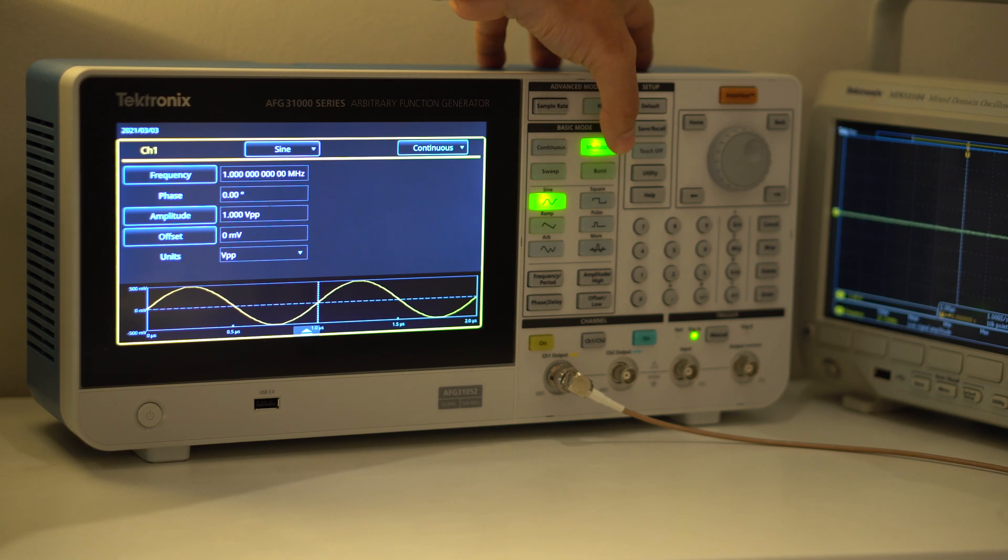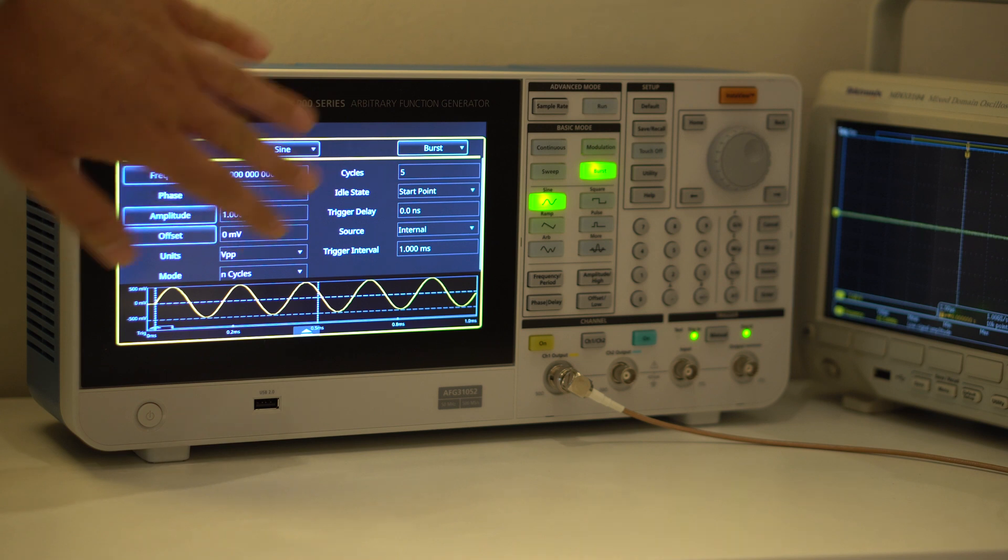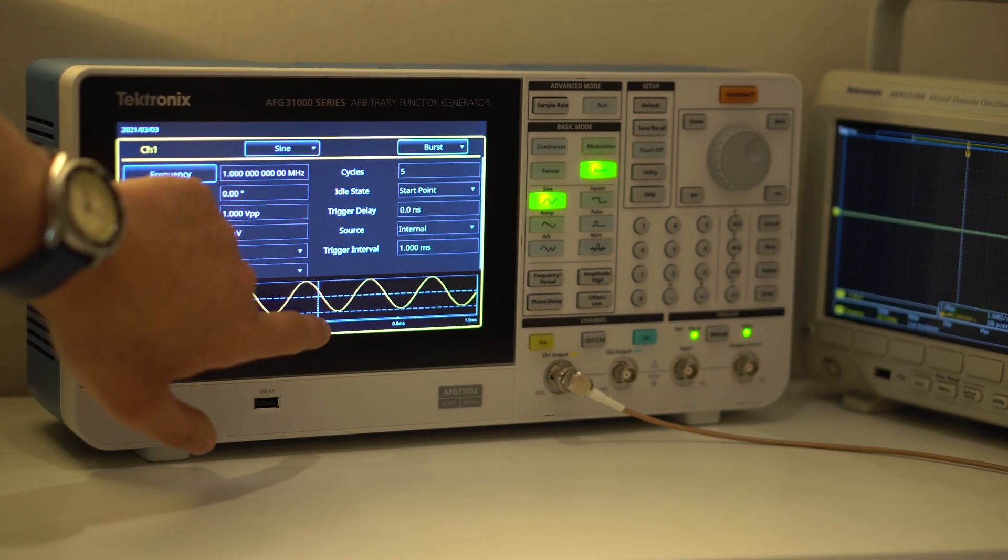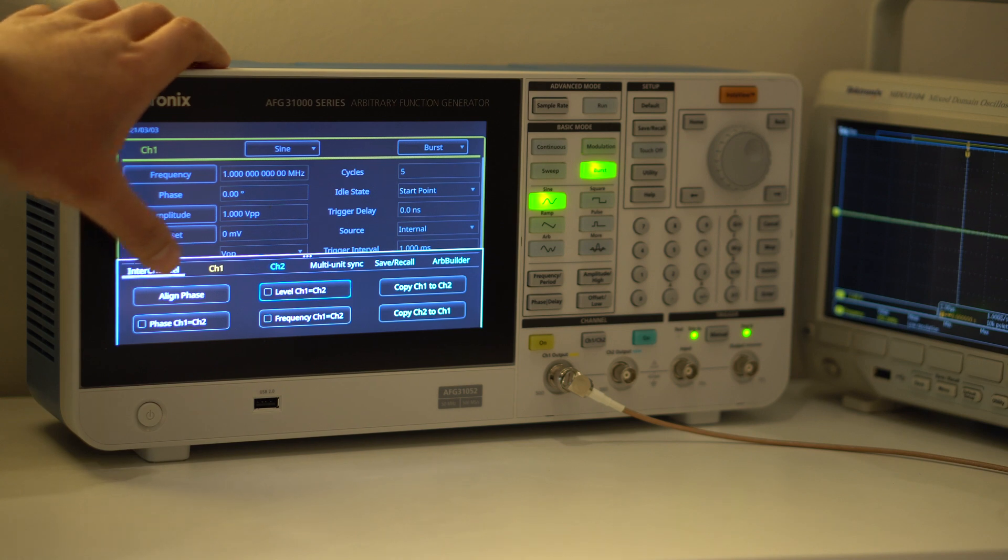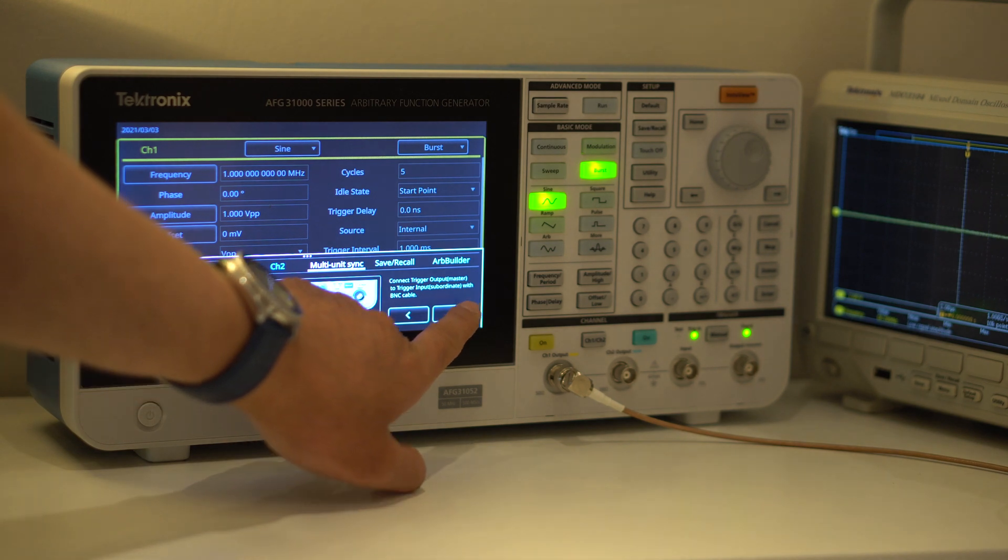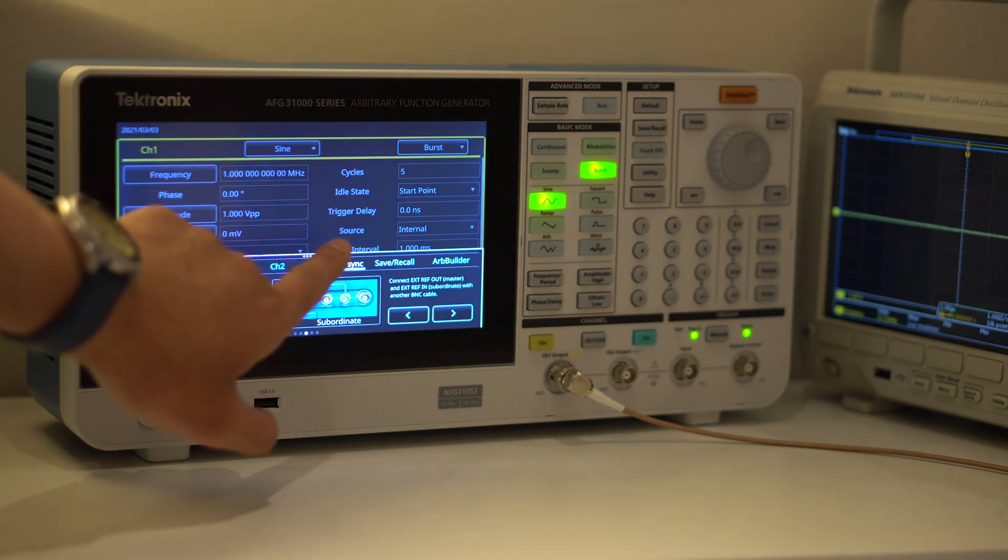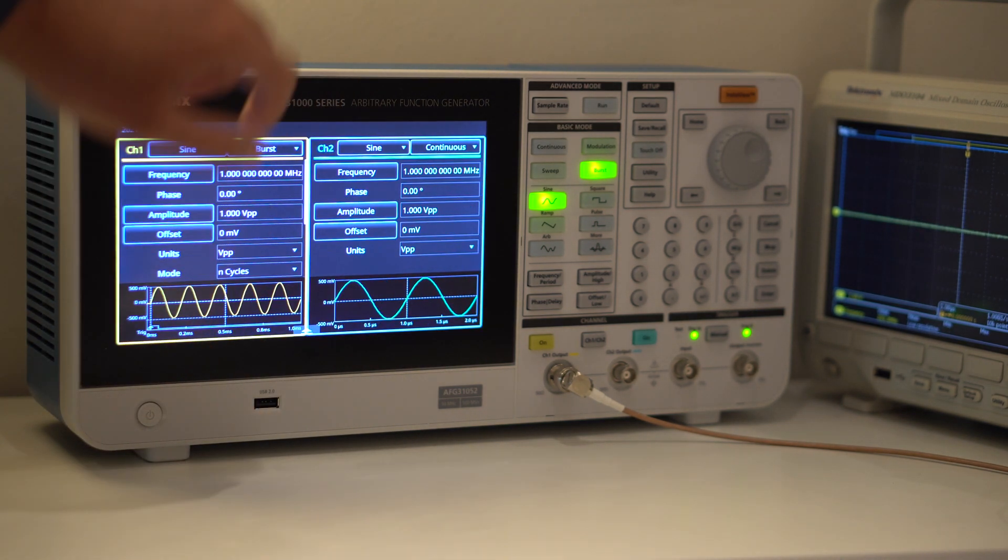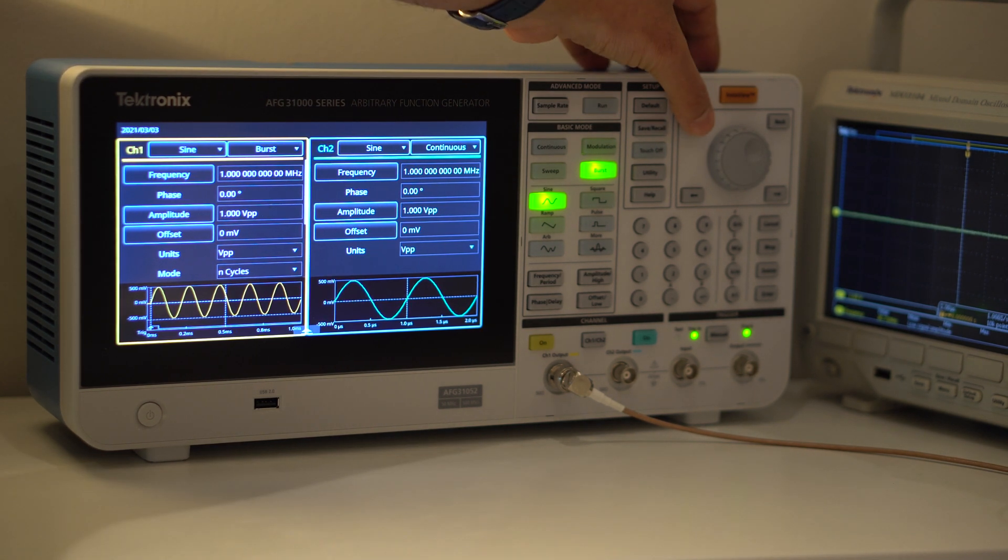If I select a more complex setting like modulation or burst mode, then more of the display gets used and it's all there on the screen at once. There's only one pop-up menu from the bottom. It contains the few minor settings which you'd hardly ever need to change, like copying from one channel to another or setting overall limits to prevent the device under test from being damaged. You can also set the load setting there as well. There's a cool capability to synchronize multiple AFG units together, and the information here walks you through how to do that. This lower pop-up menu is infrequently needed, and most of the time the user will be interacting with the channel display panes here. You can go back at any time to the main selection page by pressing the home key.